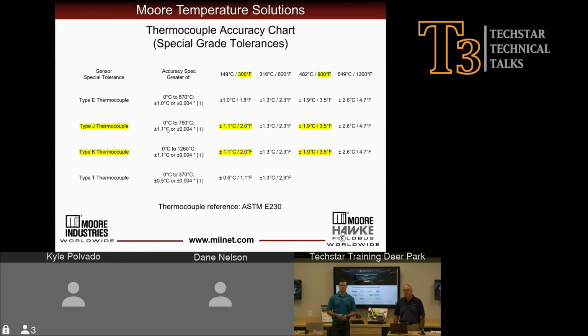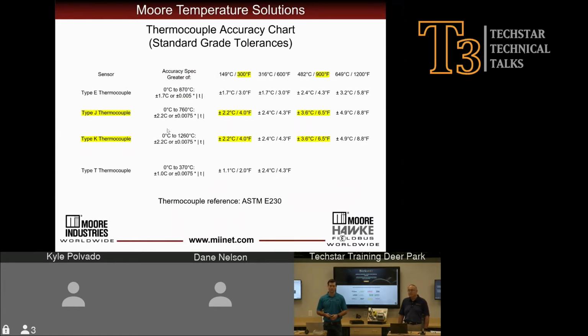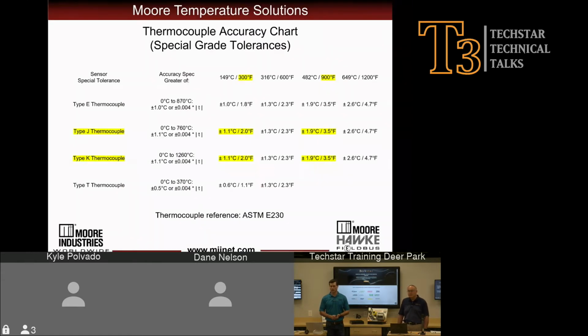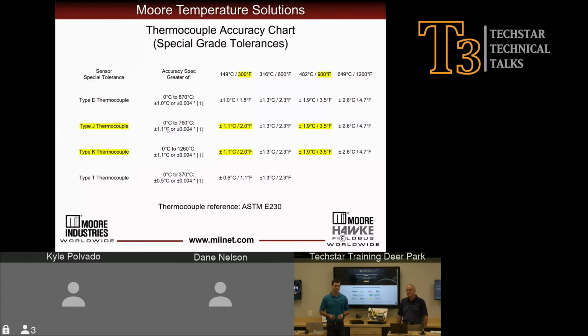Now, with anything, you can spend more money and get a better grade. You can get the Chevy or you can get the Cadillac. You can always go up in value and what you're paying for. And with thermocouples, that's not any different. So if we use a special grade type J or type K thermocouple, uncertainty now reduces to 2 degrees Fahrenheit. So essentially it cuts it in half from the 4 degrees of uncertainty that we had with standard grade wire. This special grade wire is essentially more pure metal alloys that are being used to make up the thermocouple components. I didn't cover this at the beginning, but a thermocouple is made up of 2 dissimilar metal alloys. They see millivoltage gradients across them whenever heat's applied, and that's how we take our temperature, by reading that millivoltage difference. So by using more pure metal alloys, we can reduce the uncertainty that we're seeing from a standard grade thermocouple to a special grade thermocouple.